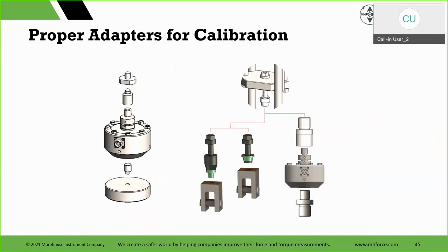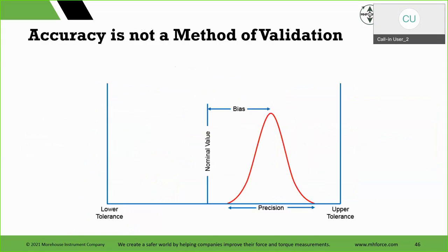So, yeah, there's adapters. Again, we're looking at how easy they are to change. And here, accuracy is not a method of validation. Many calibration laboratories have standard practices to use accuracy as a method of validation. When the device does not meet the specification, the technician will adjust it in their machine, which has unknown errors, to meet the tolerance requirements. Now we're doing an adjustment.